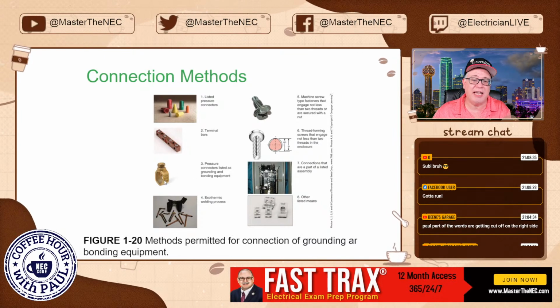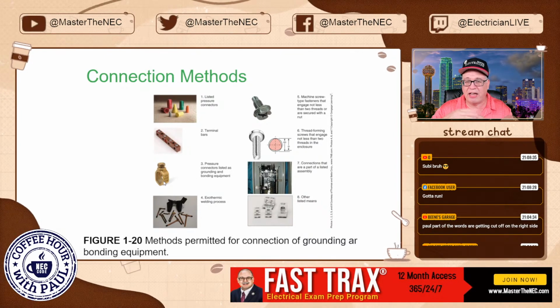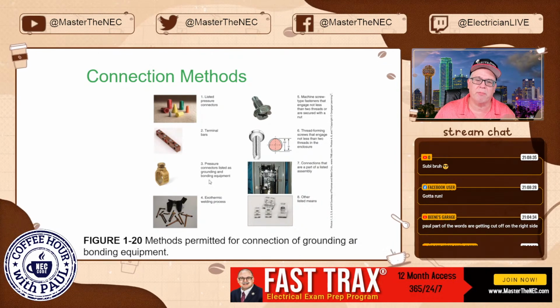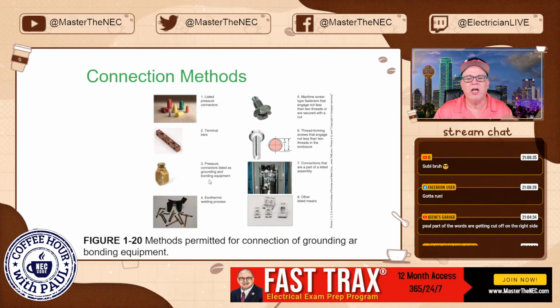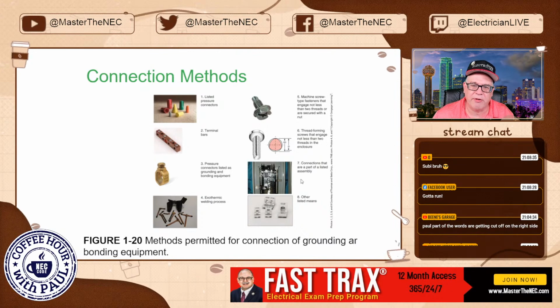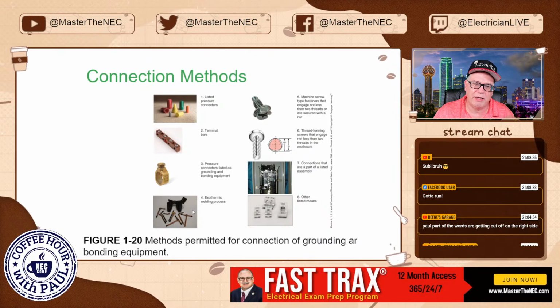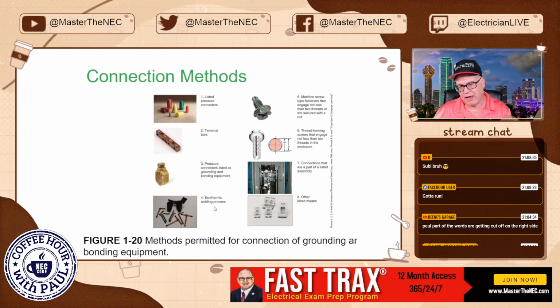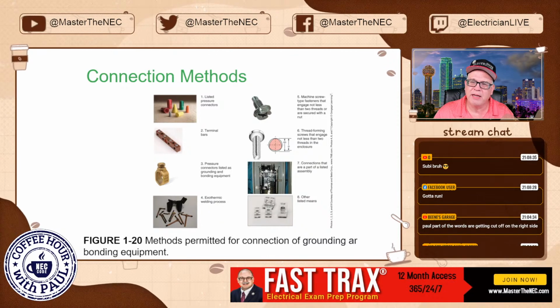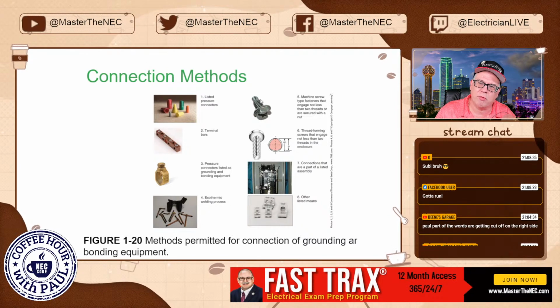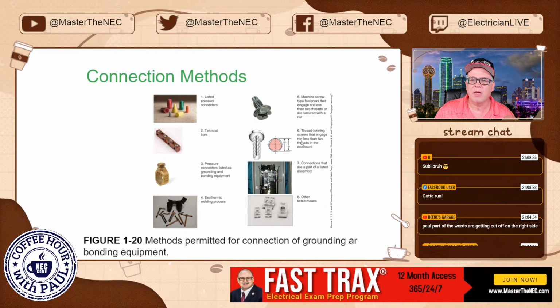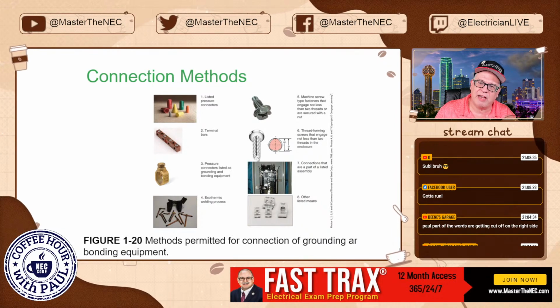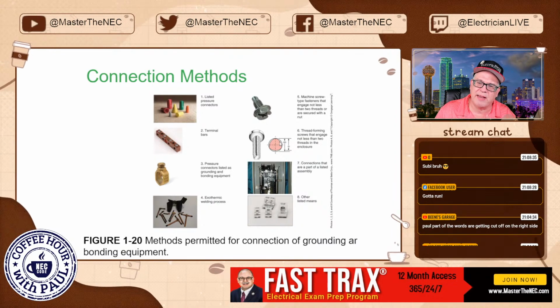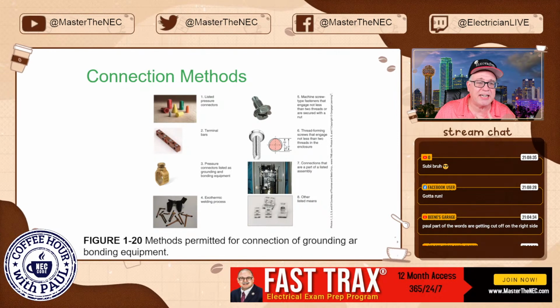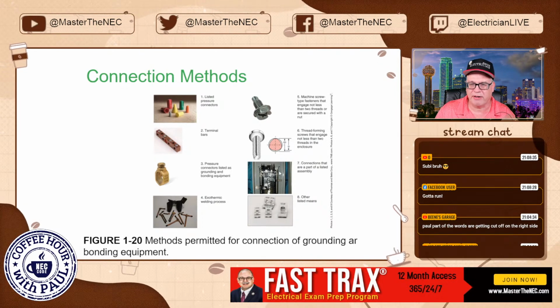Believe it or not, this is an acorn clamp. Could be a saddle clamp. Those are pressure connectors, meaning you have to apply some type of pressure in order to make the mechanism come together. Here's your exothermic welding. It's an actual process, okay, where you use a reactionary process. There you go. There's your machine screw with 2 engaged threads. Here is your thread forming screw. Notice how it has a taper cut. As you can see the taper. And then as it goes in, it actually cuts the 2 full threads that are engaged.